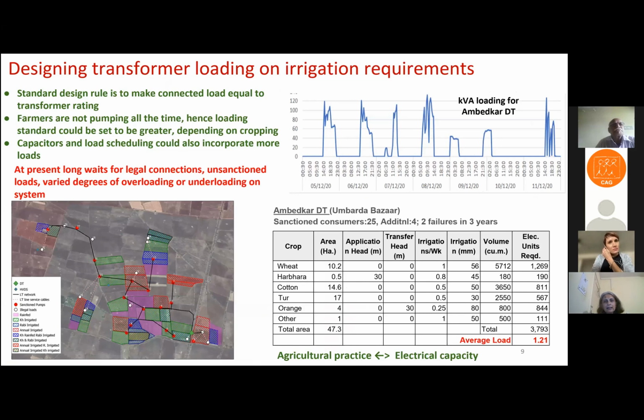The other thing we said is that currently the number of connections given out on a distribution transformer is just fixed - one transformer has a rating of 100 kVA, so they give out pumps to about 80% of that rating, loading a 100 kVA transformer to 80 kVA. However, not all farmers are pumping at the same time, so they can load it to a higher number depending on the cropping and irrigation prevalent in that region. That would allow a greater number of legal connections. Then there's the problem of connections that are waiting, but right now they limit sanctioned consumers to a much smaller degree than needed, and the rest are all unsanctioned.